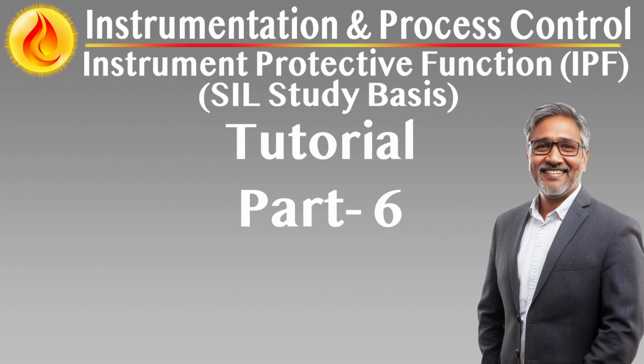Formal authorization process. Overrides may only be applied by authorized personnel and must be approved through a documented process. The reason for the override, affected IPF, duration, and responsible individuals must be recorded before implementation. Time-bound and revocable. Overrides must be applied for the shortest duration necessary. They must be automatically removed after the defined period or manually revoked after task completion, with confirmation that the IPF is fully restored.